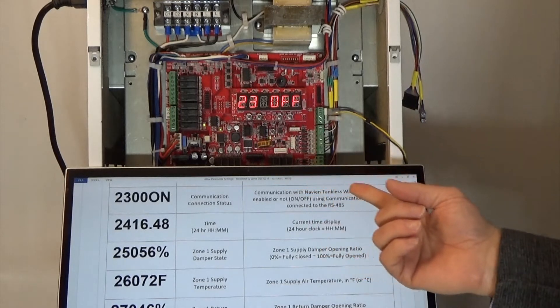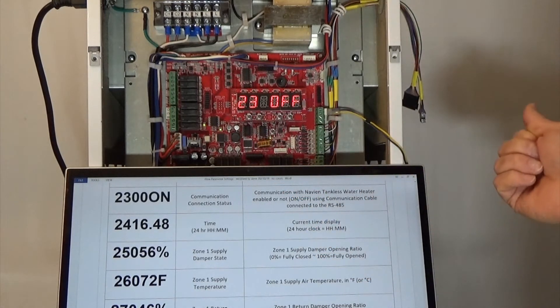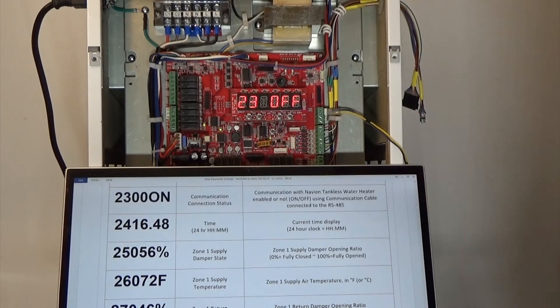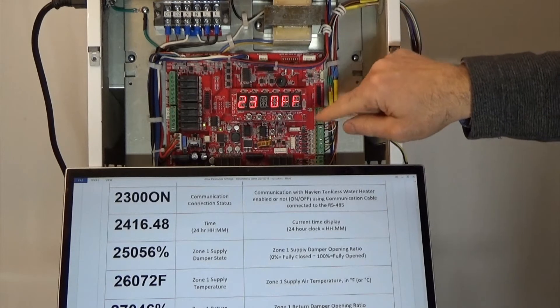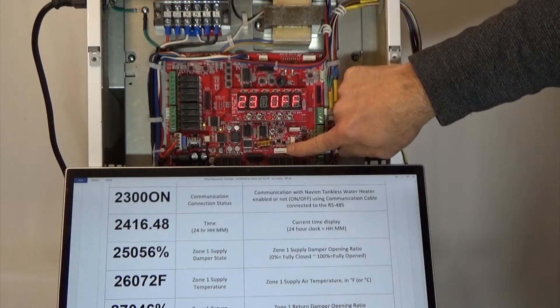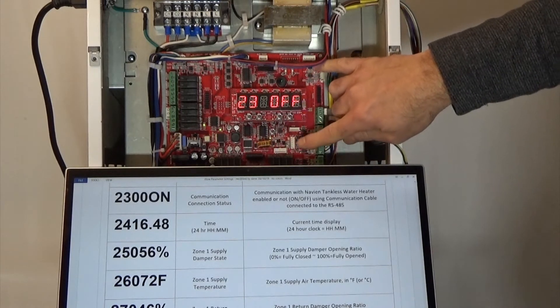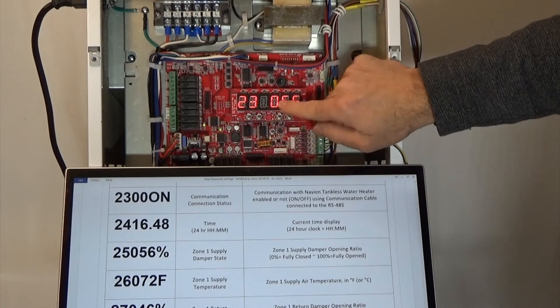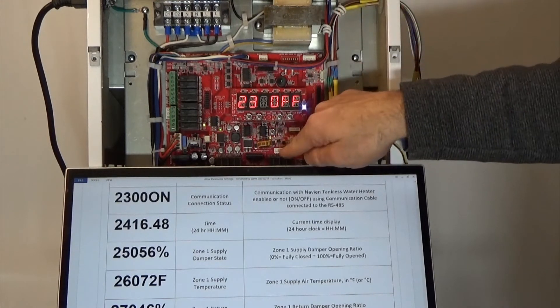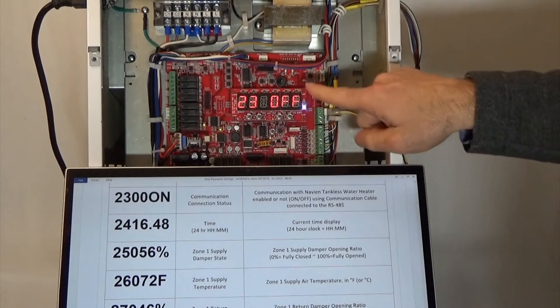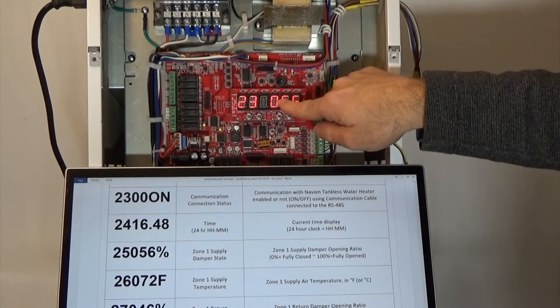Parameter 23 tells us whether or not we're communicating with the Navien. We have communication capability with Navien tankless water heaters. When using the iFlow with the Navien, go to parameter 28 on the Navien — not on the iFlow — and turn communication on. The connector for the communication cable between the iFlow and the Navien is the RS-485 connection below the display. Turn power off, plug in here, plug into your Navien, turn both back on, and they will start communicating. Parameter 23 shows whether communication is on or off.